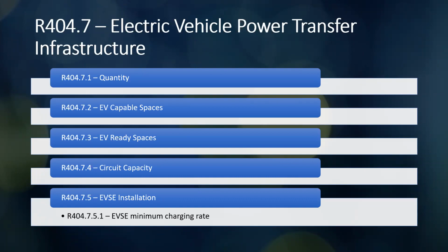And then electrical distribution equipment to which the raceway assemblies connects to has a sufficient dedicated space and spare electrical capacity for that 2-pole circuit breaker or set of fuses for that as well. So EV ready spaces, it's talking about the branch circuit serving that EV space shall comply with terminating within 3 feet, have a minimum capability in accordance to this different section in the book. The panel board or electrical distribution equipment shall have a directory that basically is labeled already that says for electric vehicle supply equipment, which is the EVSE. And then the outlet or enclosure shall be marked as such.